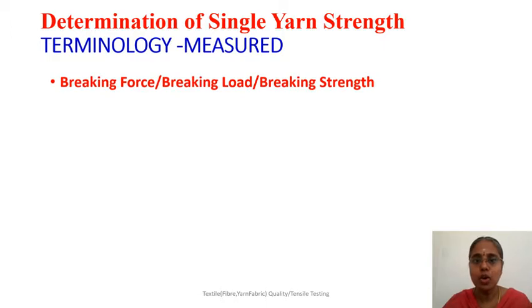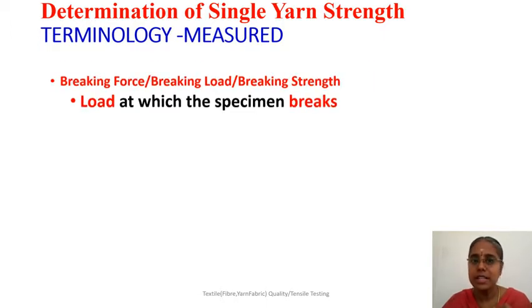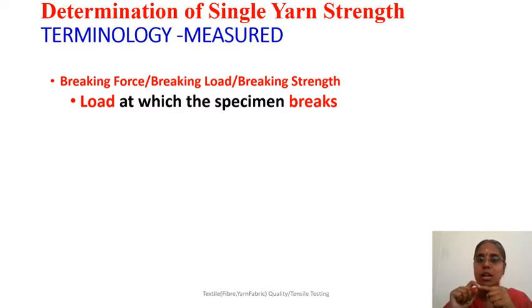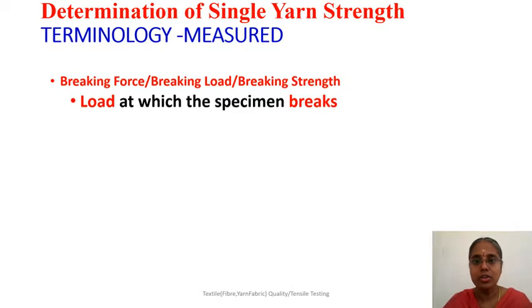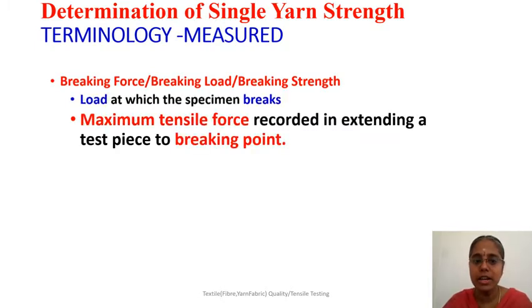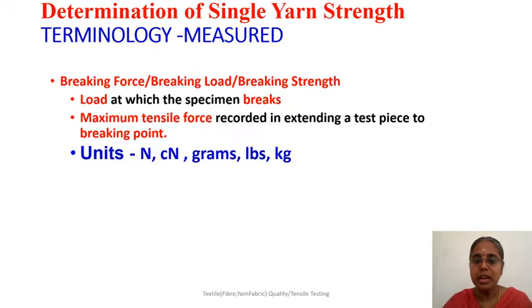Breaking load or breaking force or breaking strength is the load at which the specimen breaks. Sometimes the specimen will break after the maximum point, so it represents the maximum load recorded. It is the maximum tensile force recorded on the test load indicator during the breaking of the specimen. The units may be in Newton, centi-Newtons, grams, LBS, or kgf.